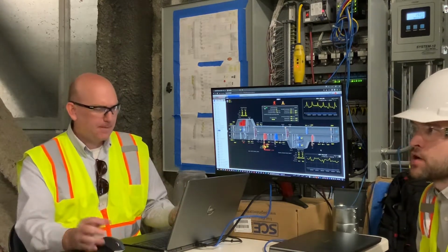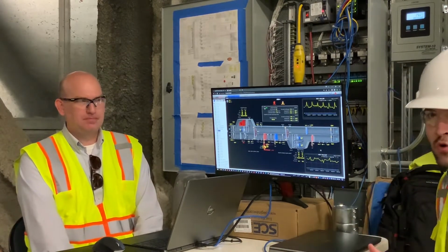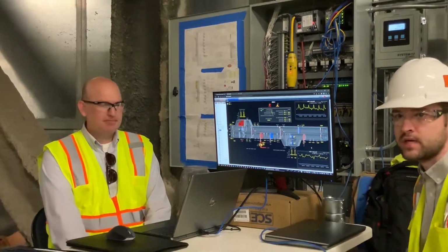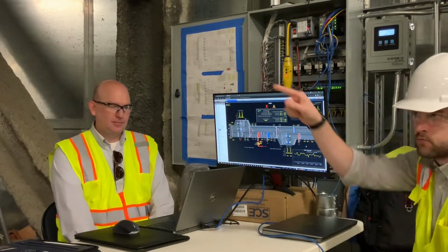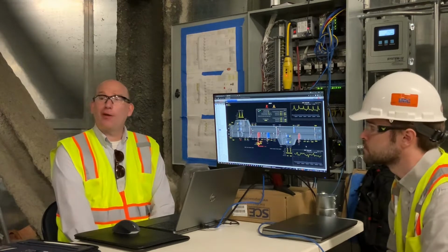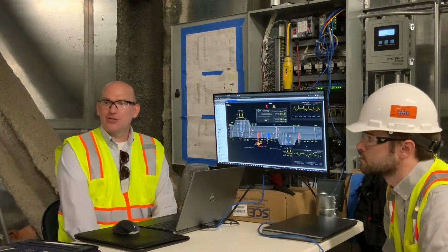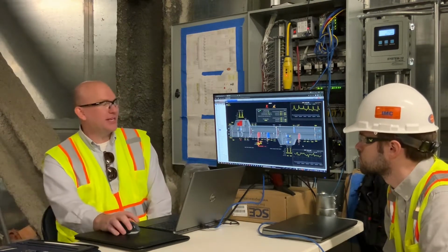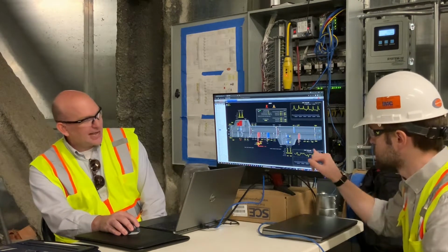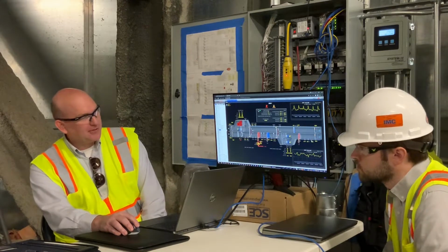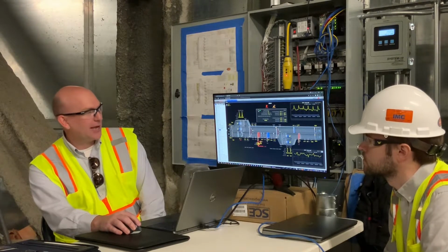And every unit has hardwired duct pressure safety, so there's not going to be a scenario where one just ramps out of control and blows apart ductwork. It'll shut down long before that ever gets there. High static and low static, supply and exhaust side, you have switches built in and a manual reset right on the side of the unit. Every point where you would have a pressure safety, it has it. There's nothing missing. I'll tell you this, initially they had us put the pressure safety here, and there's just no reason to have it there at the high pressure, so we moved it over.